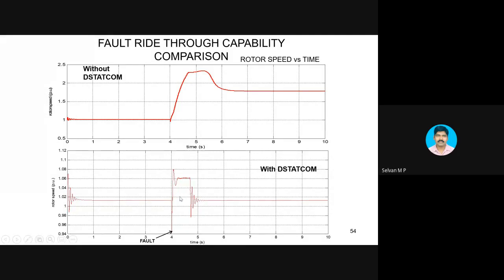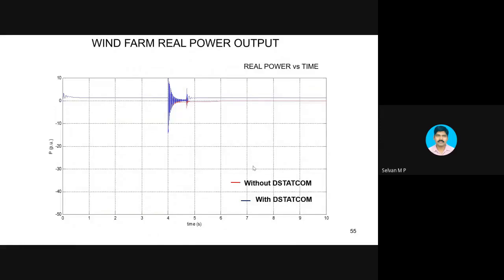And look at this. This is with STATCOM. The speed is increasing as soon as the fault occurs, but the increase in speed is less compared to this case. Here it is going enormously, which cannot be practically possible. Practically, there will be mechanical damage. But here, the speed increases slightly. From 1 per unit, it goes to 1.02, 1.06. That's all, right? So this is a practically permissible speed change. Only 6% change. It is permitted. Then you see that after the fault is cleared, the increase in speed decreases and comes back to the original value. So that is possible with the help of STATCOM. How is it happening? Because of the injection of reactive power.